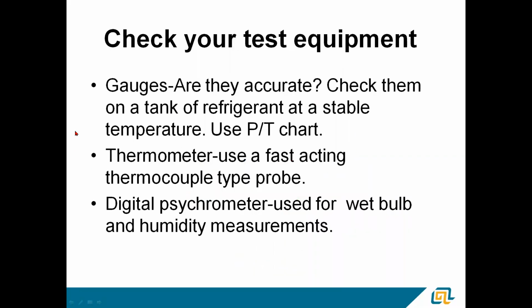One of the things that I can't stress enough is checking your test equipment. Are your gauges accurate? I went round and round with a technician about 2 years ago. We couldn't figure out what the heck was going on. And I finally asked him, I said, have you checked your gauges lately? And he found that his low side gauge was about 25 pounds off. So all the numbers we were running over that day were totally skewed. That's why nothing made sense.